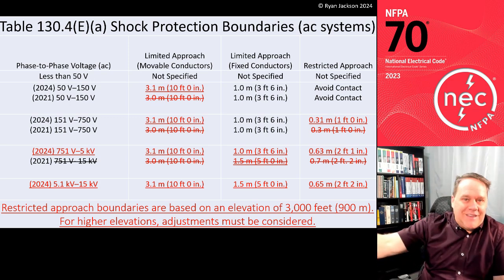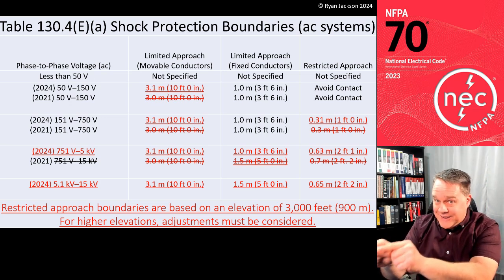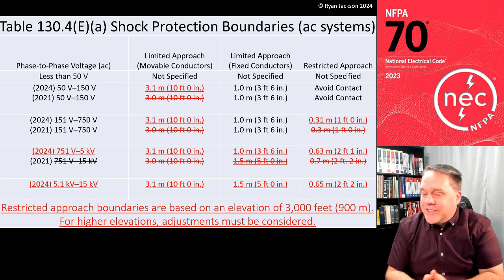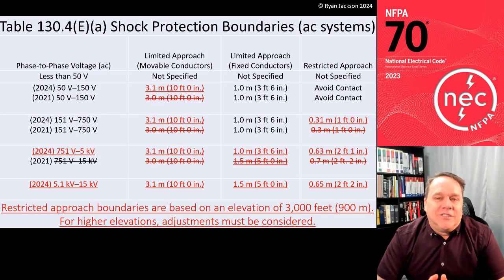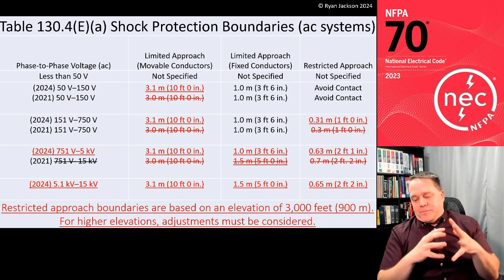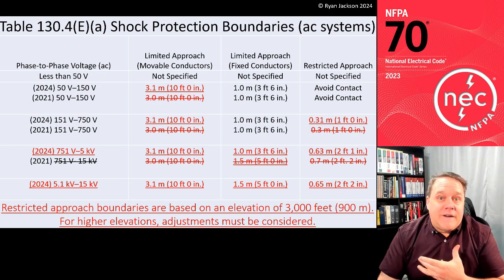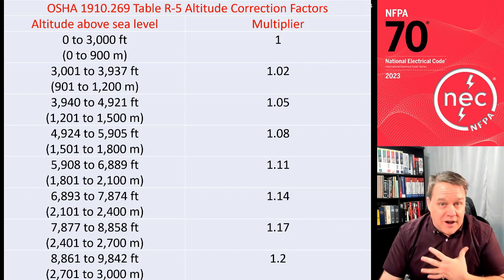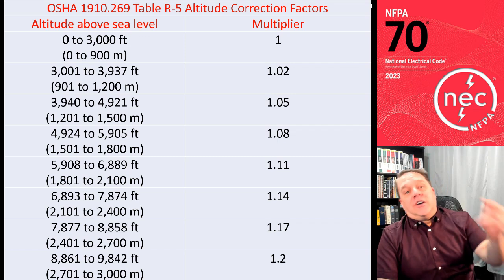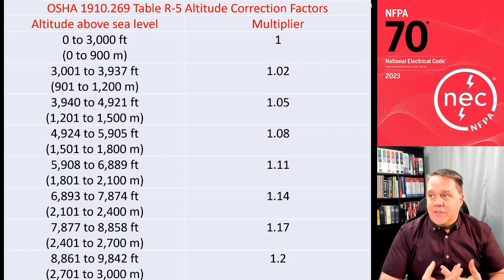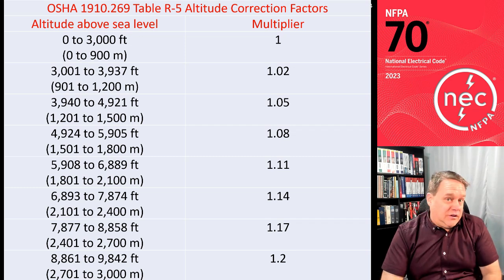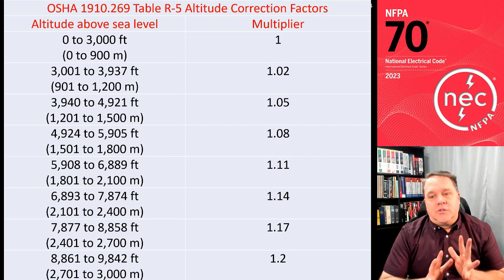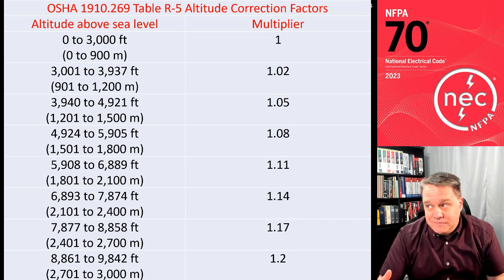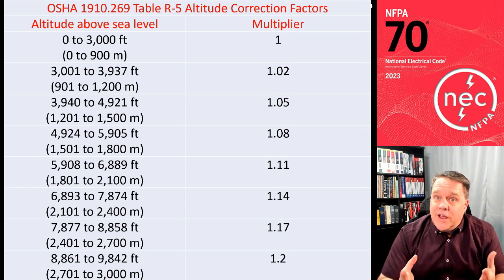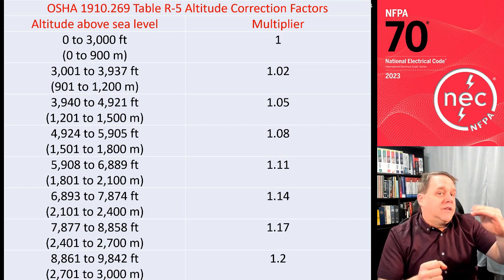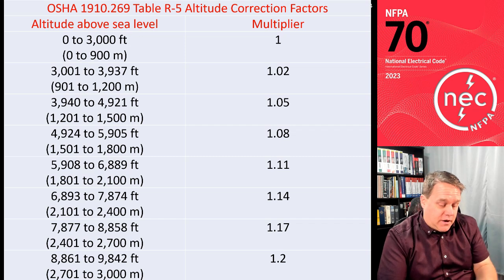And right off the bat, you have to wonder, like, why isn't it more specific? Because 900 meters probably isn't exactly 3,000 feet. For higher elevations, adjustments must be considered. Okay. At my house, I live at 5,000 feet above sea level. And when I travel and I go to sea level and then I come home, I can tell a difference in the air, right? The air is a lot thinner at my house than it is in Florida. What does that do to the dielectric strength of air? It's not the same, right? The dielectric strength of air at 5,000 feet is not the same as the dielectric strength of air at sea level.